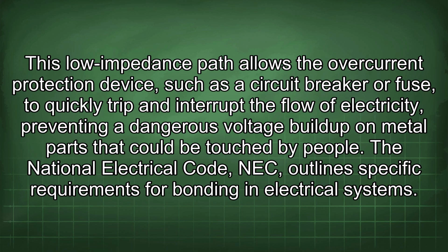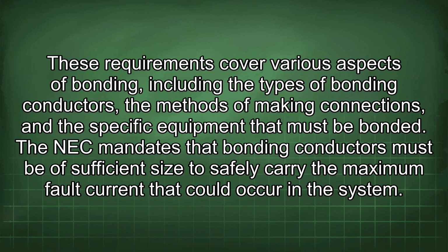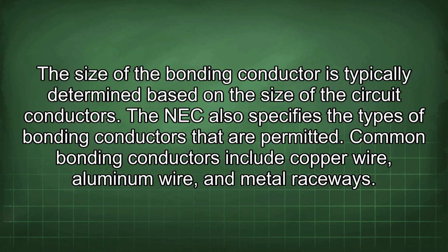The National Electrical Code (NEC) outlines specific requirements for bonding in electrical systems. These requirements cover various aspects of bonding, including the types of bonding conductors, the methods of making connections, and the specific equipment that must be bonded. The NEC mandates that bonding conductors must be of sufficient size to safely carry the maximum fault current that could occur in the system. The size of the bonding conductor is typically determined based on the size of the circuit conductors. The NEC also specifies the types of bonding conductors that are permitted.